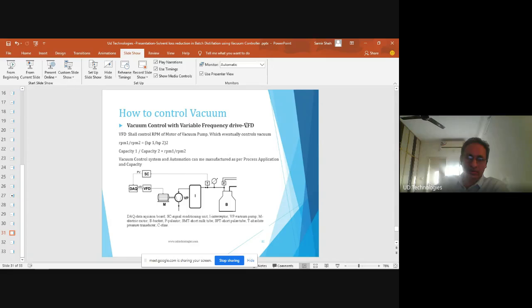The second idea is vacuum control by variable frequency drive. That is how it controls the vacuum. The VFD shall control the RPM of the motor of the vacuum pump. Like this, see, this is the vacuum pump, and the motor is there. The VFD will control the RPM of the motor, and eventually the capacity of the vacuum pump will change, so there will be a change in the vacuum level also.